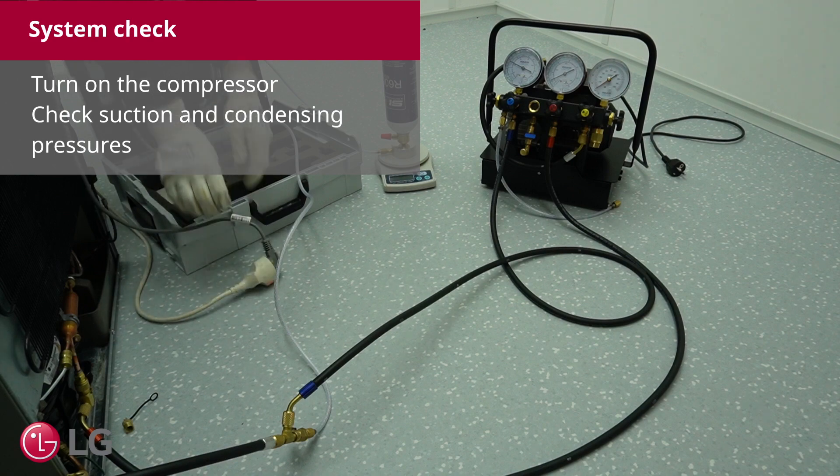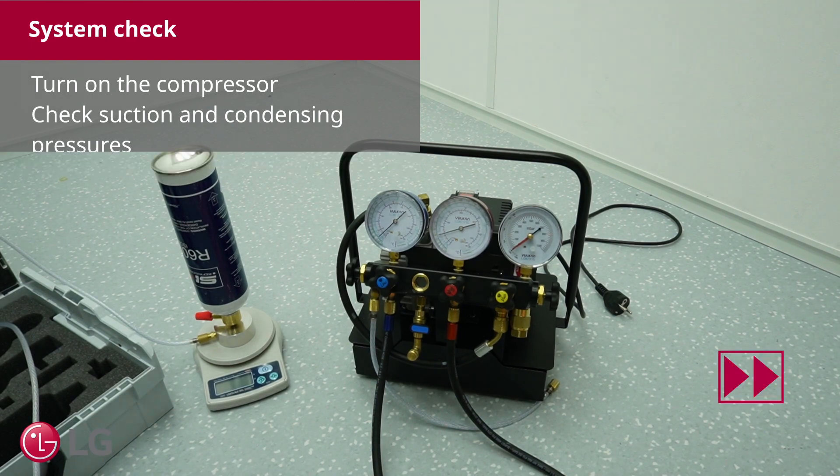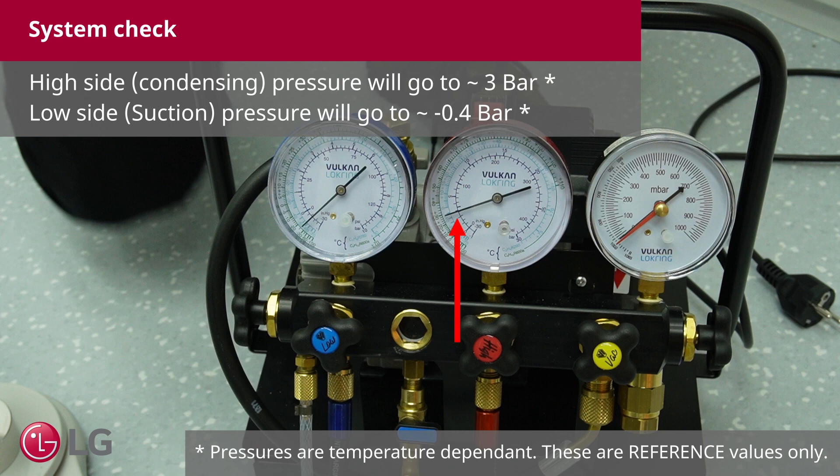Turn on the compressor. Check the suction and condensing pressures. The high side pressure will go to roughly 3 bar and the low side pressure to roughly -0.4 bar. The measured values highly depend on the ambient temperature.